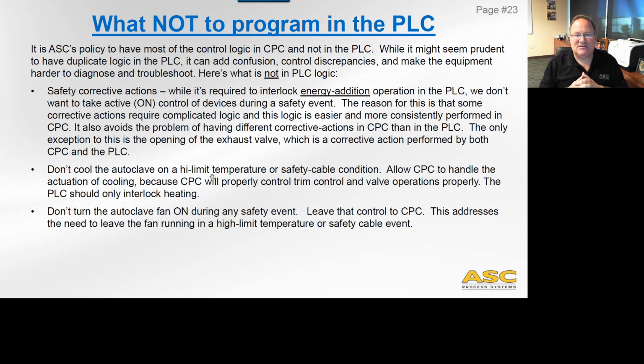And there is a bit of a discrepancy here. We have changed this policy a little bit, but before we allowed the control engineers to put corrective action in the PLC for conditions such as high limit or safety cable pulled or this type of thing. But we decided to move all that into CPC and really keep the PLC only turning things off, not turning things on. So it is ASC current safety policy now to have most of the control logic in CPC and not in the PLC. While it might seem prudent to have duplicate logic in the PLC, it can add confusion, control discrepancies, and make the equipment harder to diagnose and troubleshoot.